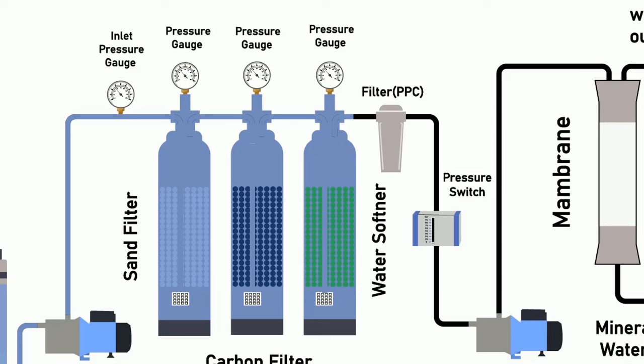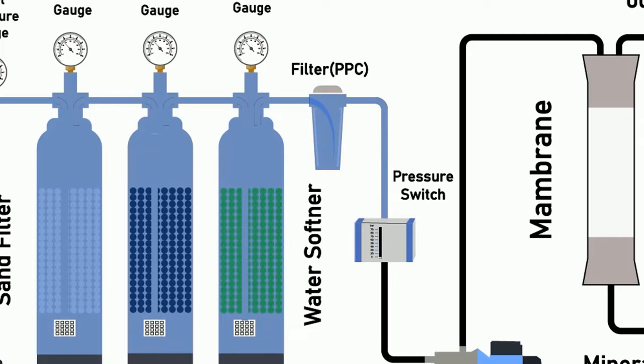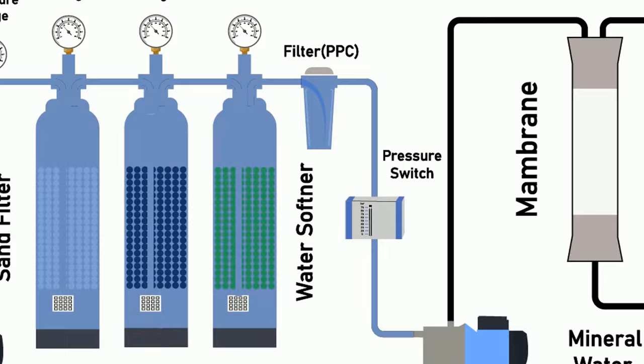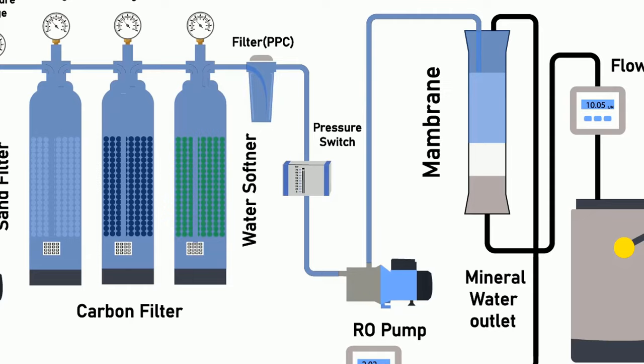Then the water travels to the PPC filter where it is further purified. After the PPC filter, water goes to the pressure switch. When the pressure of the water rises to a certain level so that it can travel to the membrane, the switch gives a signal to the control panel and it starts the RO pump.